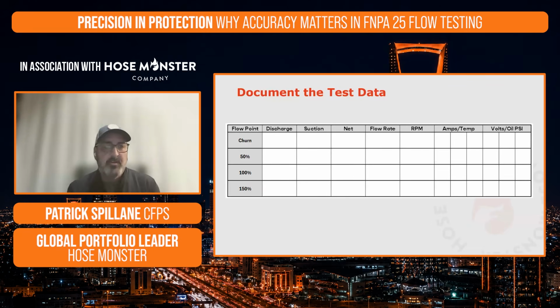So this would be just a quick template of the documentation that we need to verify for every fire pump test. When we first turn that fire pump on, we call that our churn test. When that fire pump is just turning water, we're just churning water. We're not actually flowing water. So at churn, we want to document our discharge pressure and our suction pressure. We're going to calculate that: discharge minus suction will equal our net. We need to determine our flow rate. Here for the churn, that's going to be 0 gallons per minute. And then we need to find out how fast that fire pump is moving. And then we need to document our amps and volts, which we'll talk about in a few slides.